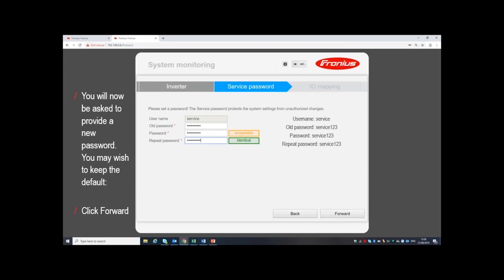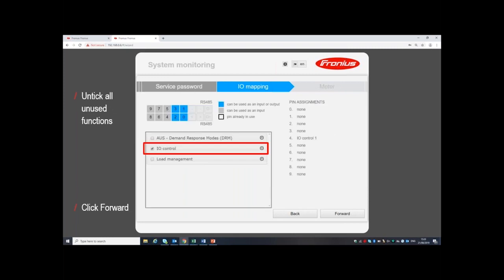You'll then be asked for the service password again. You can always keep the old 'service123' standard, or you can put your own one in. I would only recommend using a bespoke password if you're setting export limitation, just to protect that from anyone interfering with it at a later date. The next thing you see is IO Mapping. IO Mapping is for using the input and output controls on the data manager. If you're not in Australia, you don't need the Australian demand response modes. If you're not controlling it using something like a fast shutdown switch or emergency stop, and if you're not putting load management in, you don't need to have any of those ticked. For the most basic installations, untick all of those and the pin assignments will all go to none.